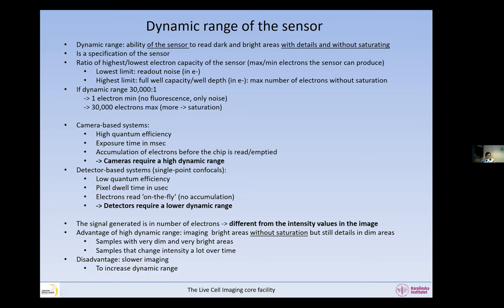What can we do to increase the dynamic range? It is a characteristic of the sensor, but we can play with the noise. The dynamic range maximum is fixed, but the lower part involves noise. If you can decrease the noise, you increase your dynamic range. On a camera, you can lower the readout rate — this lowers the readout noise and therefore gives a higher dynamic range, but imaging will be slower.